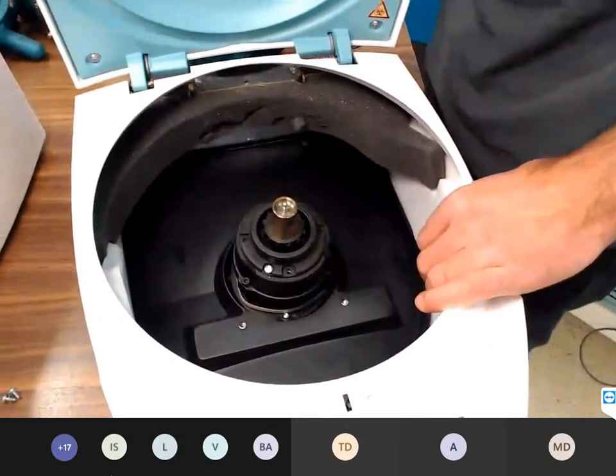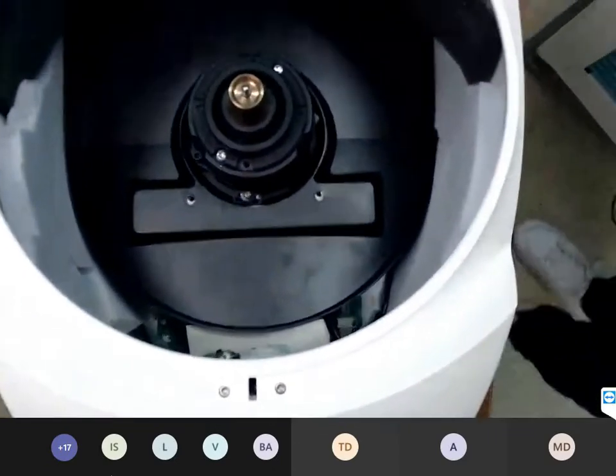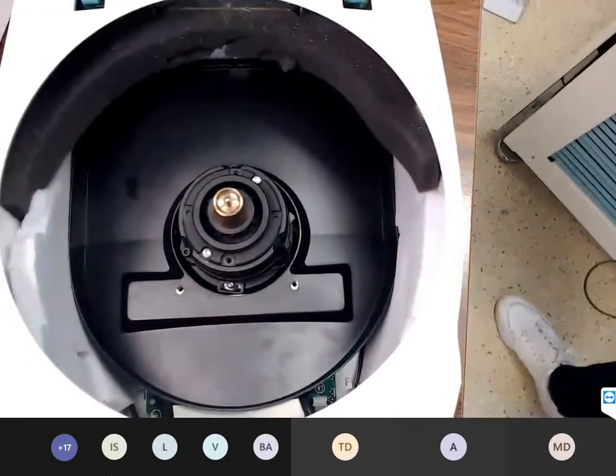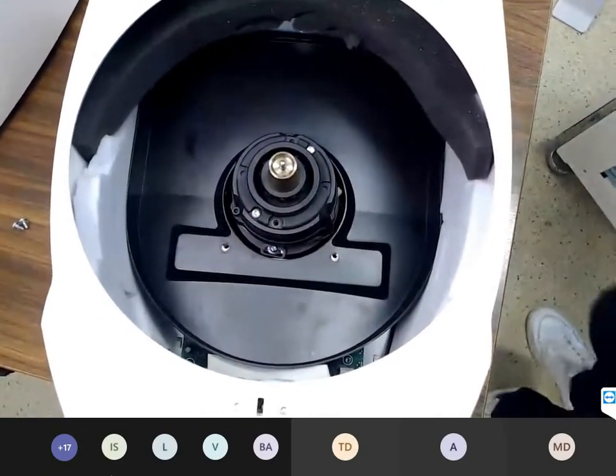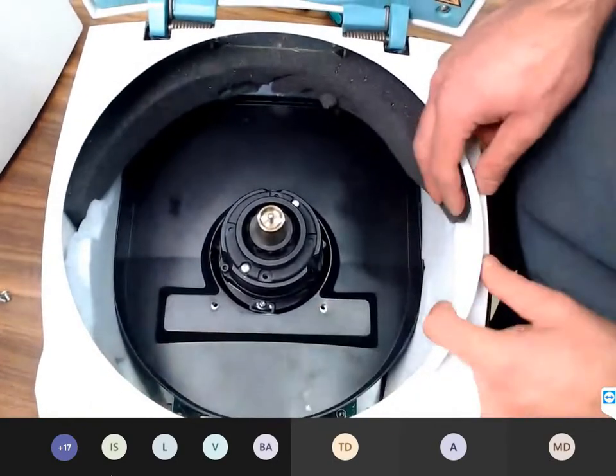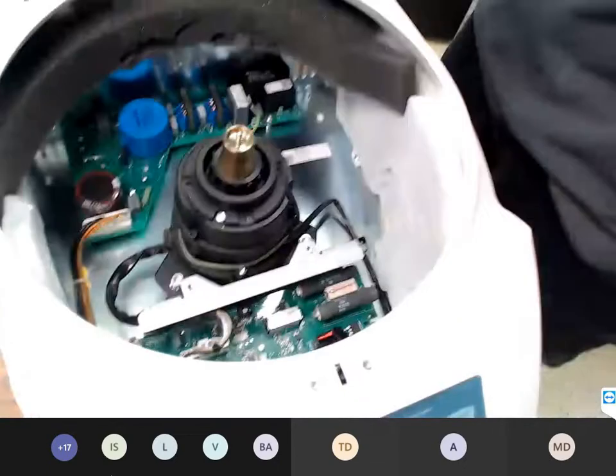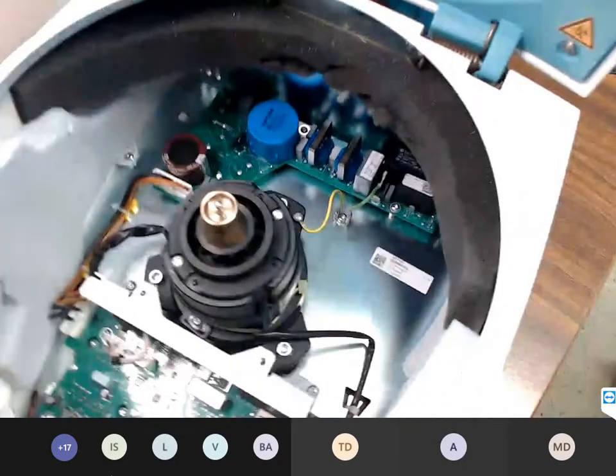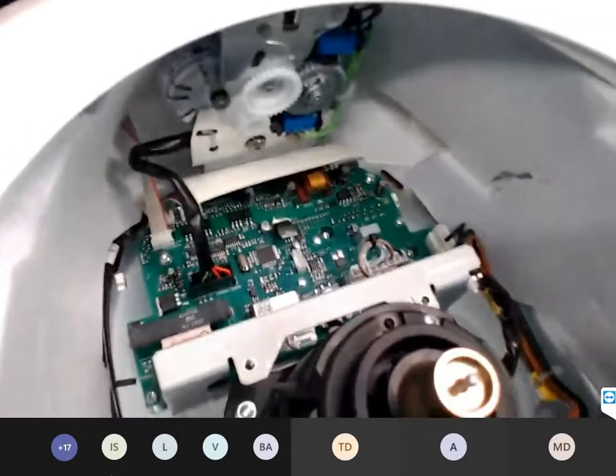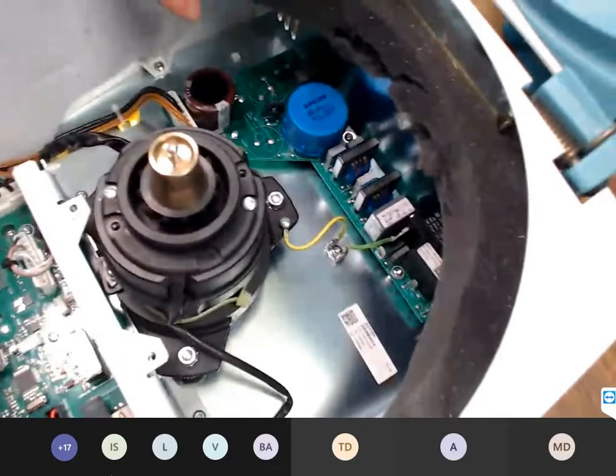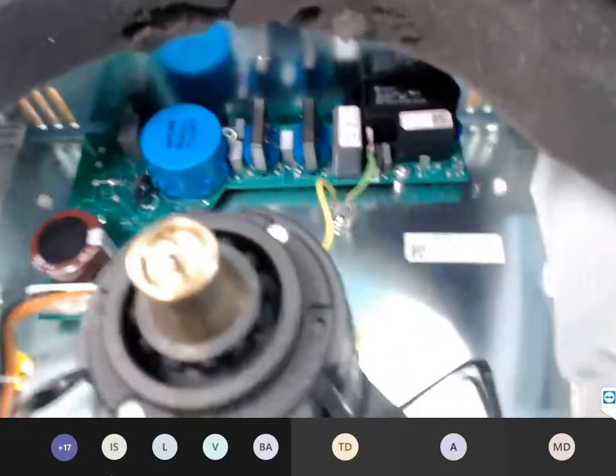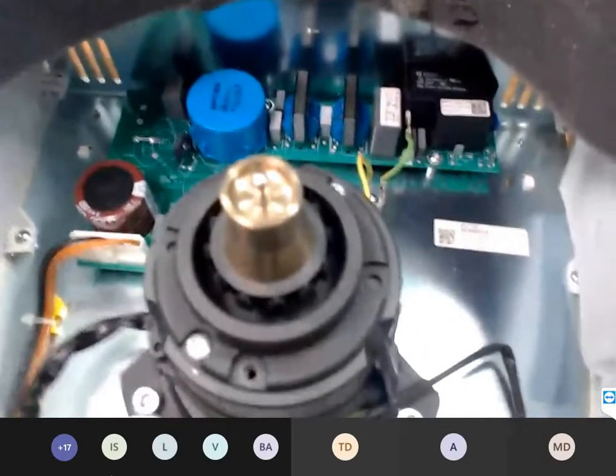So now we can see here a black part that is liquid protection for this device. We have on the side here, right and left, mats for the vibration and the noise. Remove the black parts. And now we can see the same inner part design of the micro and hematocrit. Here on the back side, the power input electronics is the same, with the same order number and the same technical design of the electronic boards.